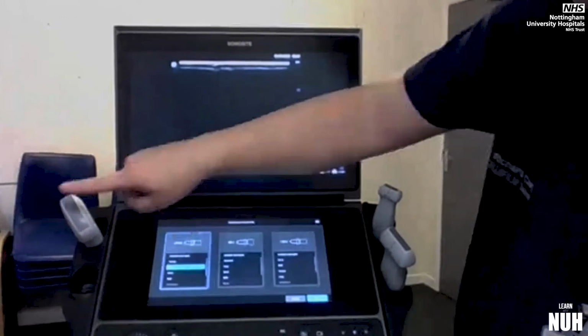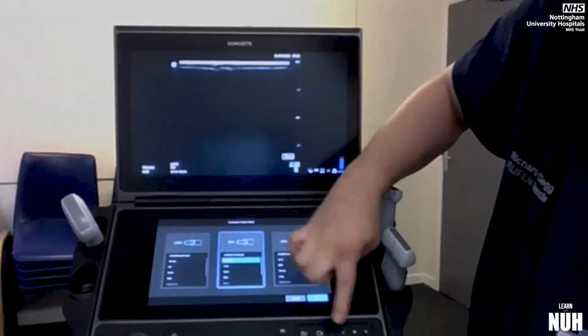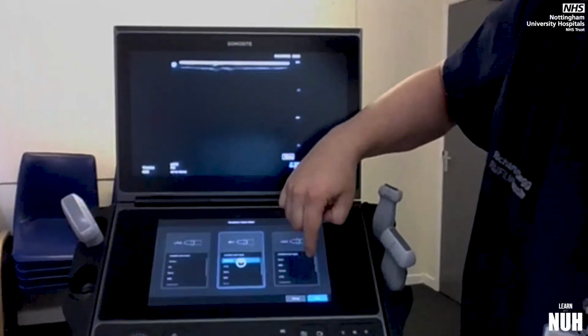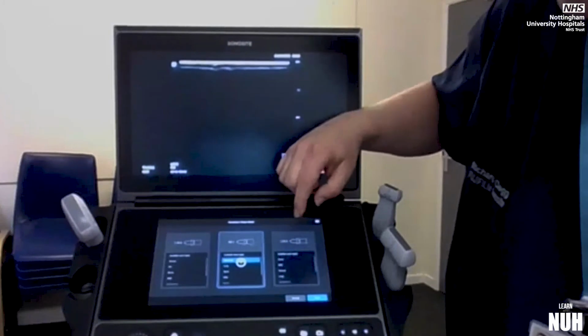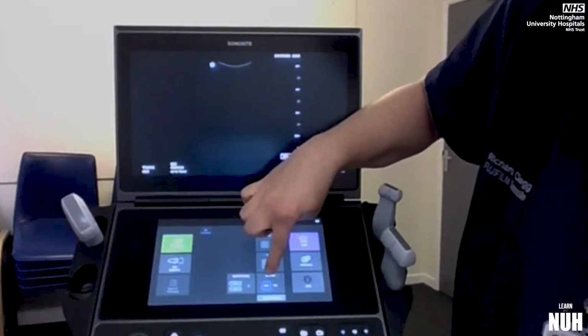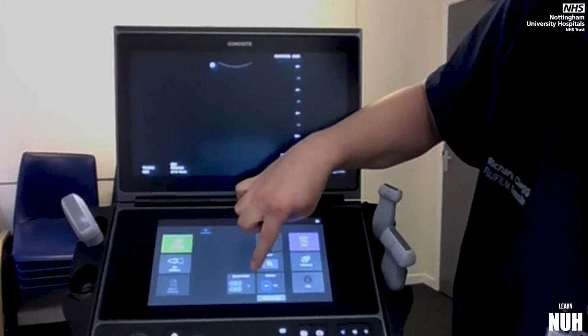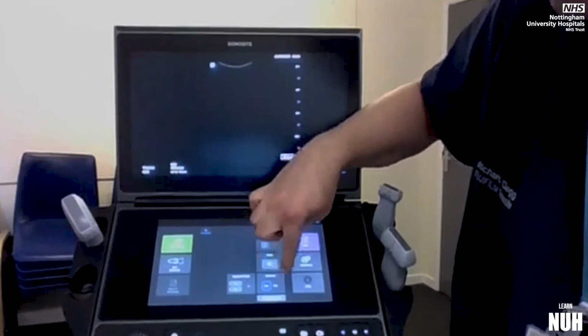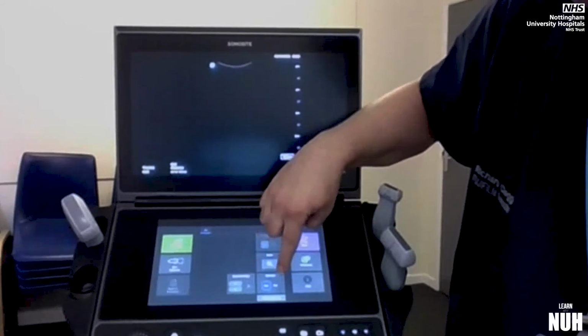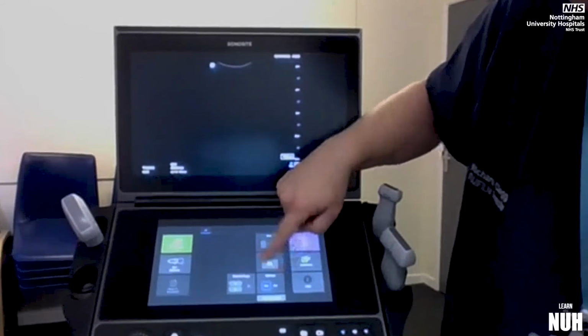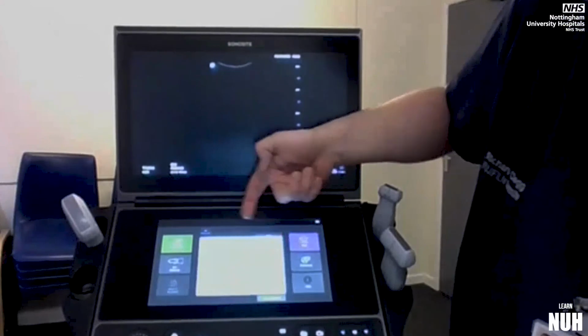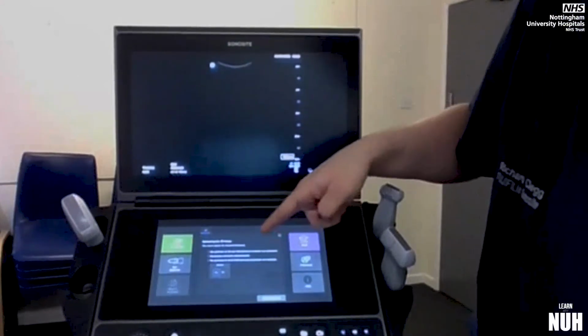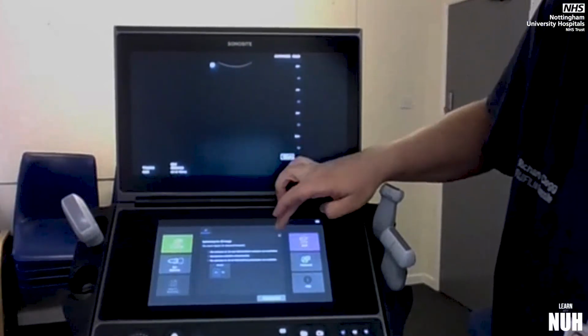If we go to the curvilinear probe, there'll be another option for that, which will be penetration. So that's your high BMI bariatric option. So it's dropped the resolution preset off, and we've got a penetration setting. So that's your high BMI one. If you hadn't a clue what all that meant, press the information button on it and it will explain it. Maybe a bit jargony, but that's where it is.